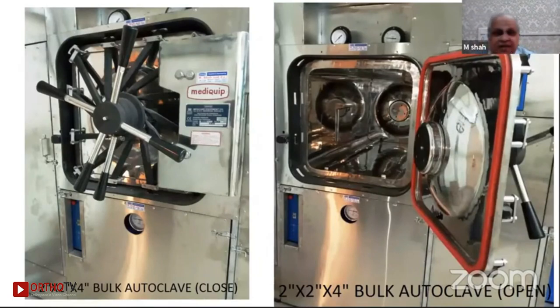Perhaps Siddharth will take it, or otherwise I will tell you this: the thickness of the chamber should be minimum 3 to 5 millimeters. Many people use only 2 millimeters and say, sir, we will work, no issue. Our autoclave is cheap. Please don't fall into that trap. You can always go for a standard autoclave.